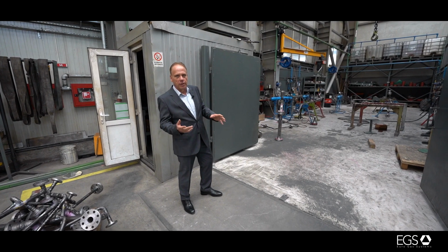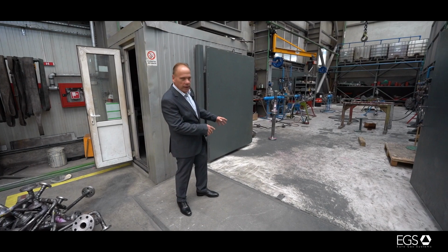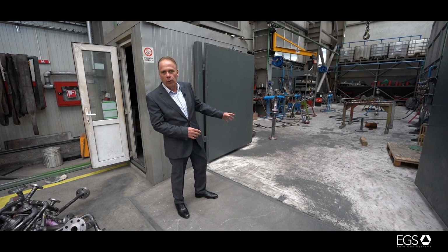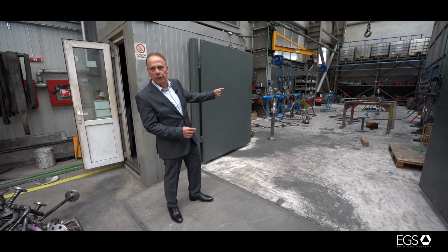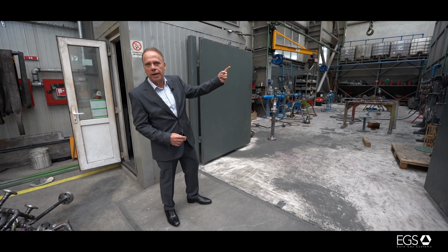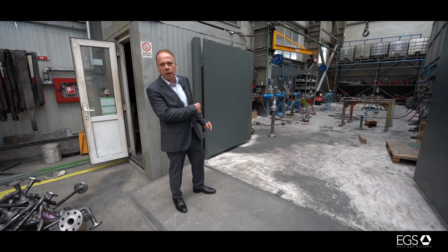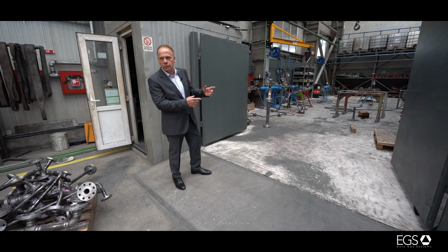At the completion of the hydrostatic test, we simply pull the plugs out of the vessel or pipe being tested, drain the test liquid back onto the floor, which gets pumped through a filter system back up into the storage tanks. This serves 2 purposes: we're not dumping test water into the storm drain, we're recycling it.